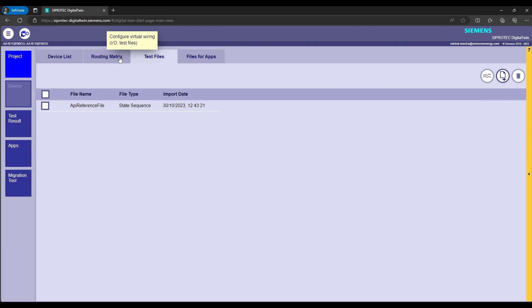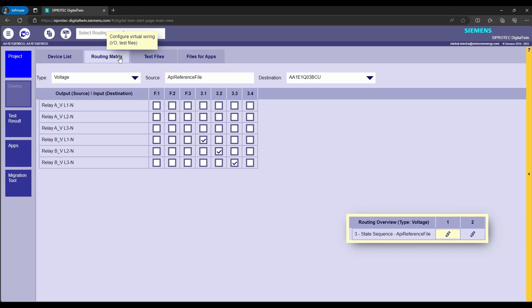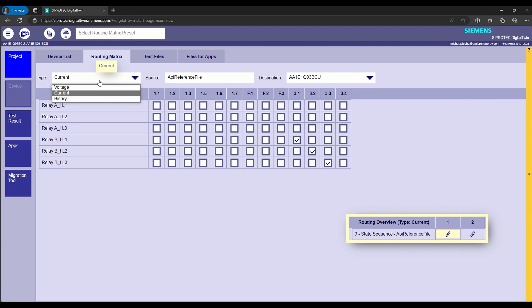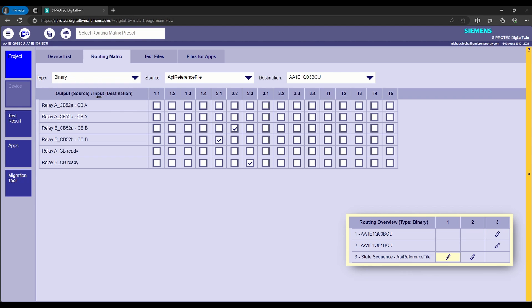we are making virtual wiring and assigning analog and binary signals in the routing matrix tab. We recommend starting the assignment with the voltages as it's presented, then currents, and at the end, binary signals. But be careful when assigning the binary signals.